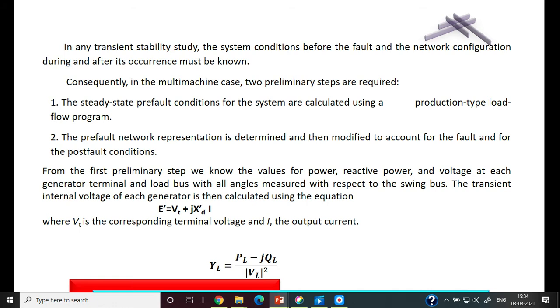In any transient stability study, the system conditions before the fault and the network configuration during and after the fault must be known — that is, we need to know the pre-fault conditions, the power transmitted and reactance during the fault, and the power transmitted in the post-fault condition.